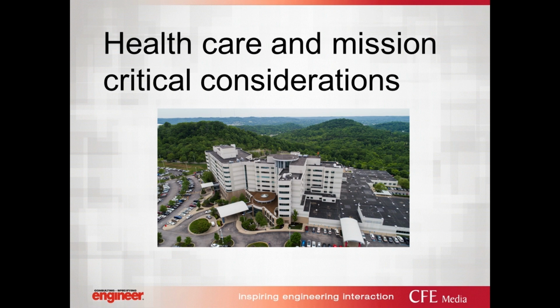Next, we must assess systems that are critical to the operation. While everybody instantly would go directly to the emergency power supply system, or EPSS, we've actually found in studies that the normal power supply system is a critical piece of operations and life safety. We want to look for single fail points. ATSs, or automatic transfer switches, can become one of these single fail points where people will need to interact, and potentially could have to interact with an energized system.